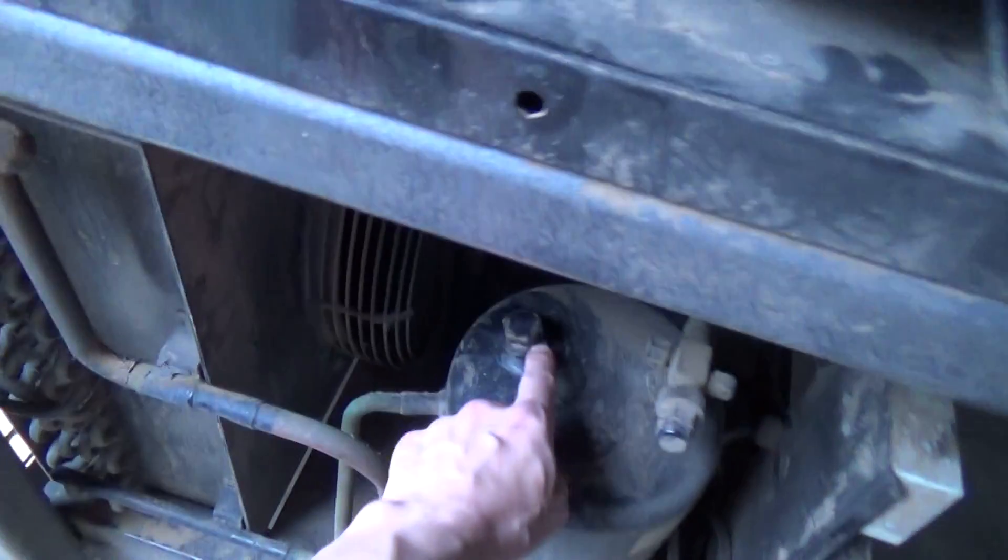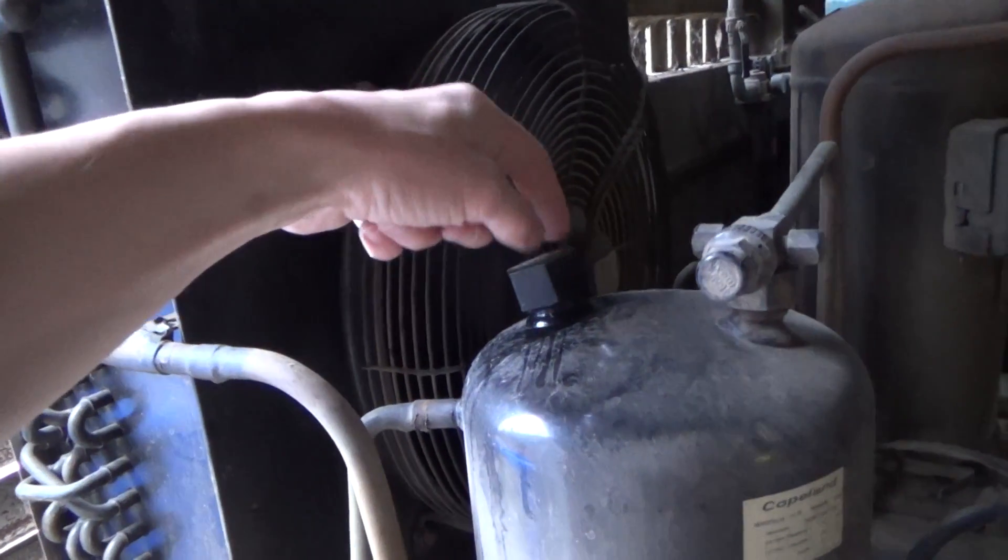We've got a leak showing on the fusible plug threads. And we've got a big leak on this one here, that's got a rubber o-ring and then they perish.